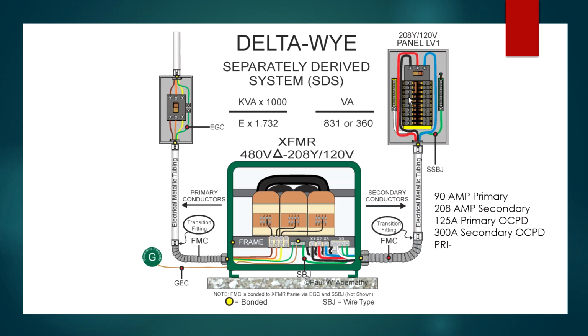No problem. Even if this was 75 kVA and they used the 300 amp device here, then these conductors would have to be sized based on 300 amperes, and that will result in a 350 kcmil conductor, because a 300 only has 285 amps, and we can't use the next size up rule here. And you're going to see that as we look at the code a little bit, but you can't use the next size up rule like you can on the primary side. On the secondary side, these conductors have to have the full ampacity of whatever the device or the equipment rating is. In this case, if it was a 300 or a 200 or whatever it would be.